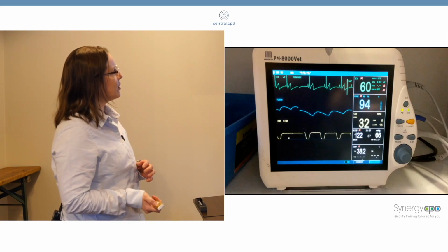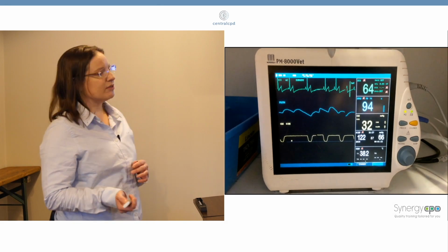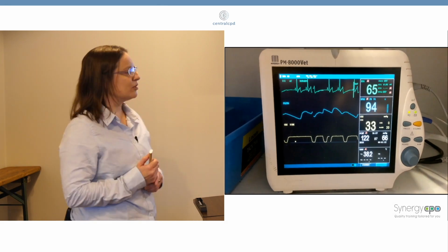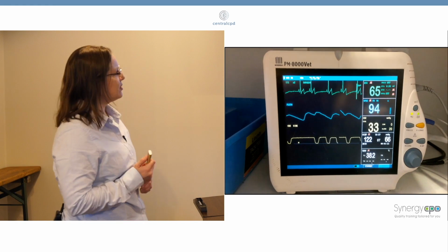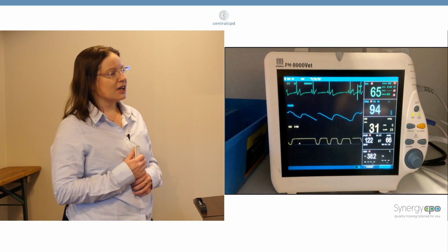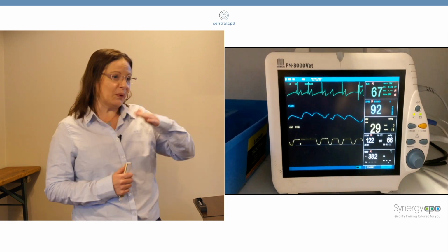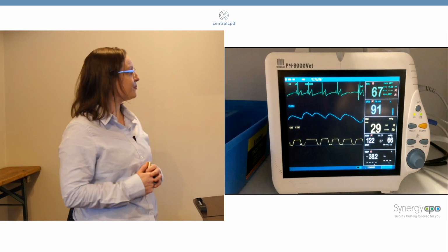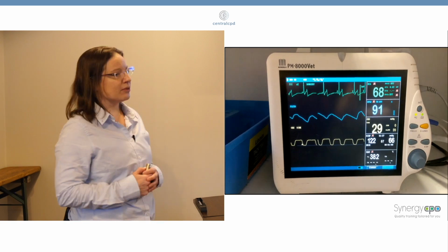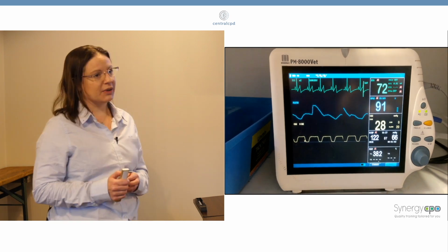So a little video here. Hopefully you can see my video here. So the capnograph, as they're breathing in, breathing out, breathing in, breathing out. Hopefully you should get a shape on your capnograph that looks like a line of little elephants following one after the other. Nice and smooth and regular breathing, always hitting the baseline when they breathe in.